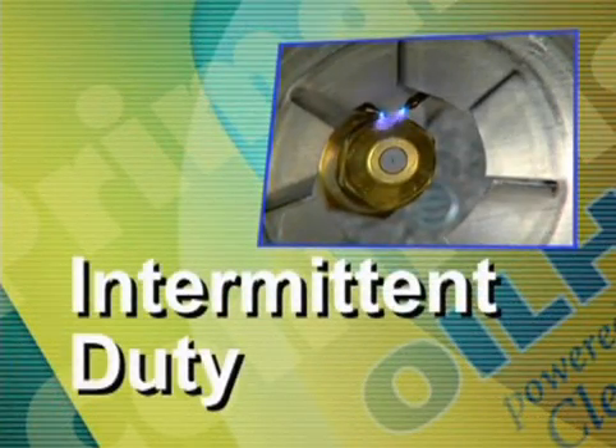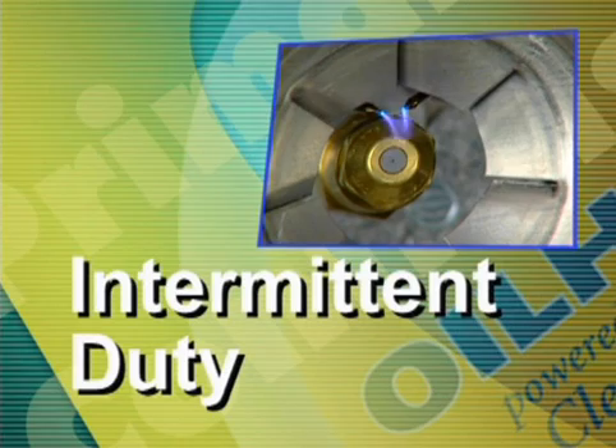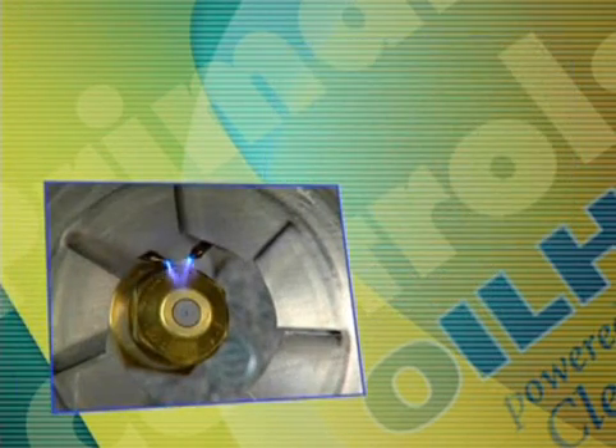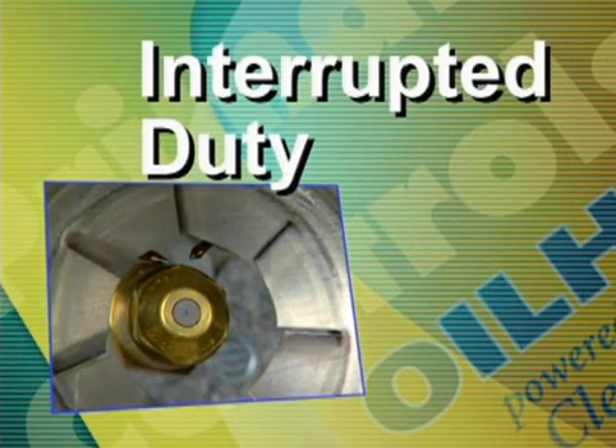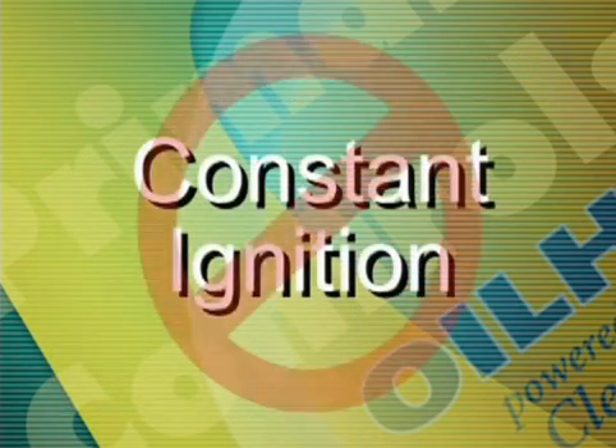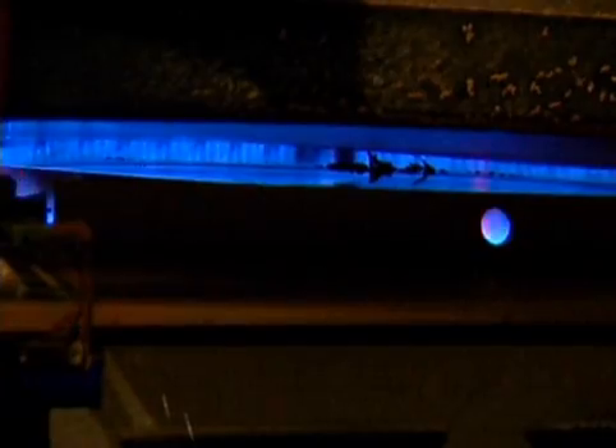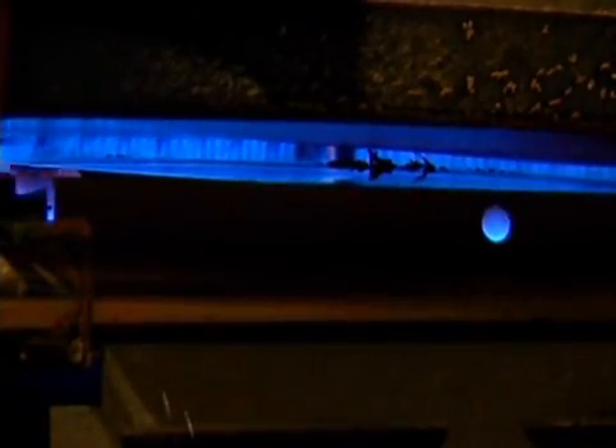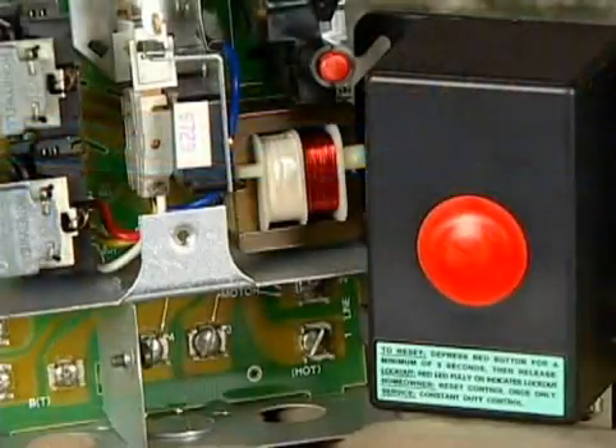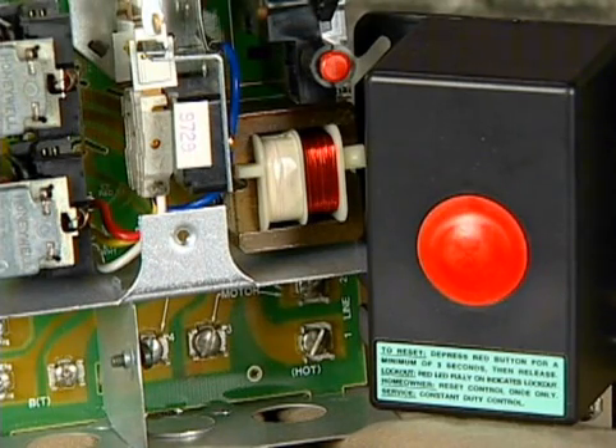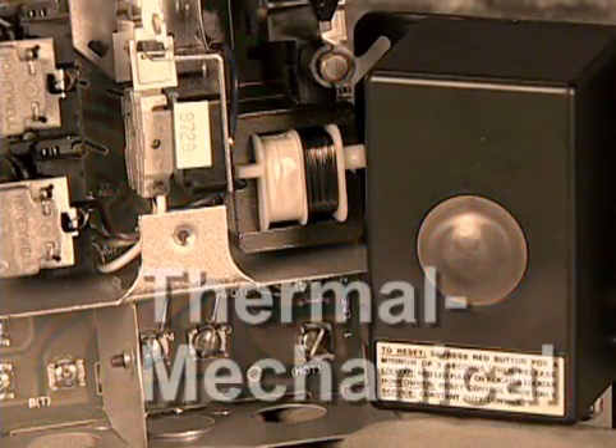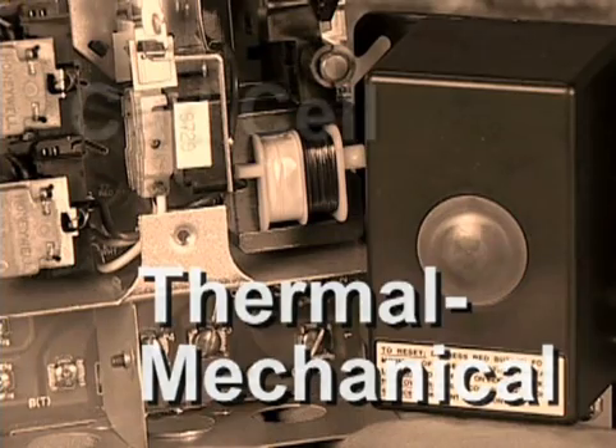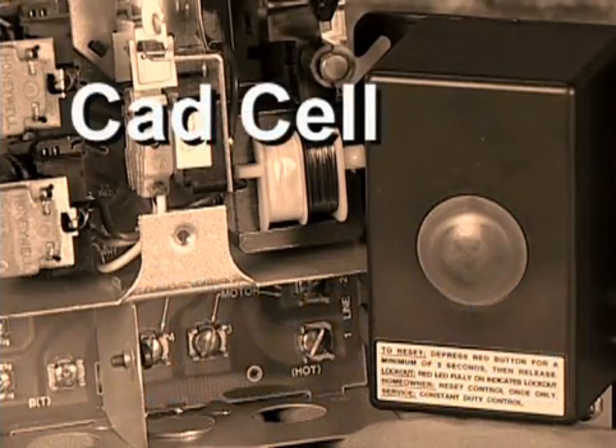To review, with intermittent ignition, the spark is on for the entire time the burner is running. With interrupted ignition, the spark comes on at the beginning of each cycle and goes off after flame is established. The term constant ignition is no longer used with oil heat systems. It is used with gas systems that have a pilot light that's always on, regardless of whether or not the burner is operating. There are two basic types of primary controls commonly found in the field today: thermomechanical primary controls and CAD cell primary controls.